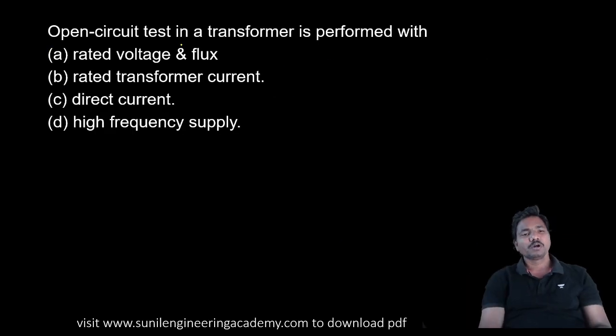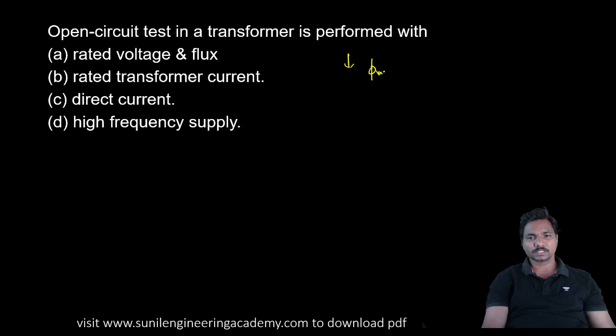Coming to the next one. Open circuit test in a transformer is performed with a dash. Just now I have given: open circuit, rated flux. If you want to get rated flux, you have to use rated voltage and rated frequency. So rated voltage and rated frequency condition.